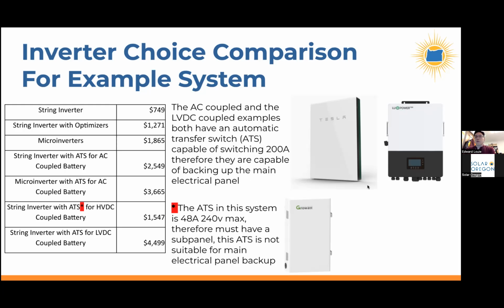And the inverter that is shown in the example for the low voltage DC battery setup also has a 200 amp transfer switch built into that inverter. Whereas in this example, the automatic transfer switch for the high voltage DC coupled battery example is actually only capable of 48 amps, so not sufficient to transfer the main circuit breaker panel in the house to be able to safely island. But 48 amps is more than enough to transfer a sub panel of critical loads to island. And so in order to use this transfer switch, you would need to figure out which circuits on the main panel are critical loads, have the electrician install a sub panel, and then move those circuits over to the sub panel.